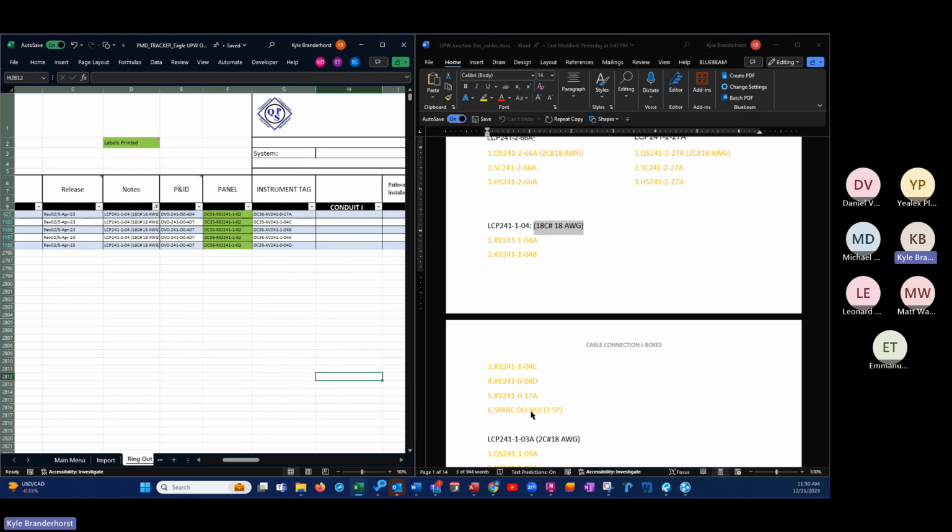And did you find that looking at the connection drawings? Yeah, that's why I say you got three spares. I don't know, Matt, if it's for future use or not. Maybe you know, or maybe this is an open item that we need to close. When we're bringing these spares, we have a 19 or 819 conductor cable. Are we just not landing them, taping the ends off or what? Yeah, tape off the ends and just tuck it in the conduit inside those analytical cabinets or the J box.